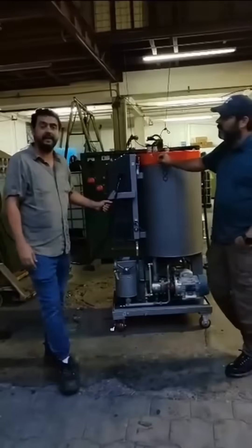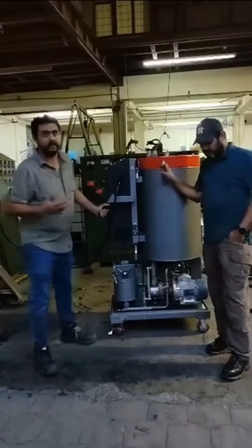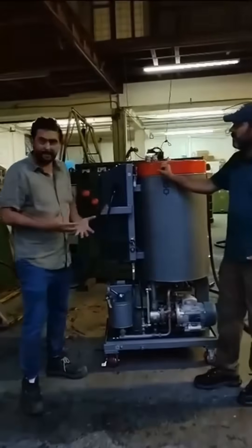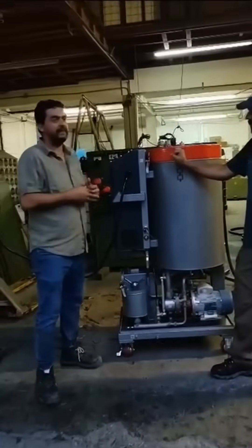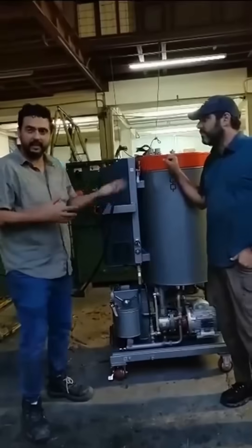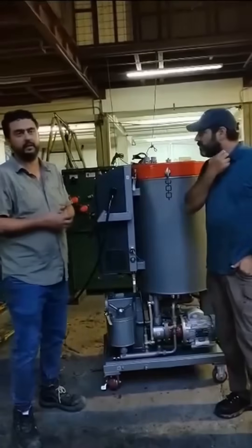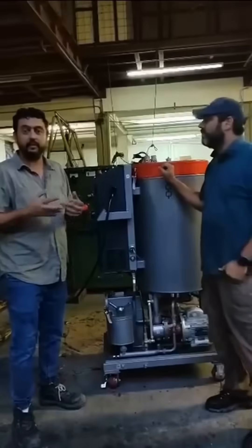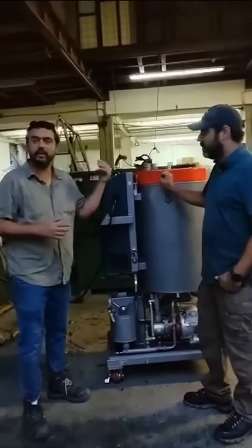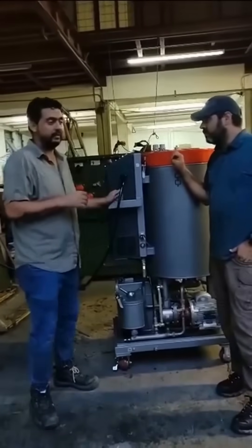To extend the lifespan of the transformers, it has meant a step up in the technical aspect. Everyone in Costa Rica sees this machine as compact, fast, and aesthetically pleasing — it really catches the eye. People ask what this device is, and we explain it is a thermal vacuum oil machine used to recondition transformer oil. Many people are unaware that oil, even if new, must be processed and reconditioned before entering the transformer tank.